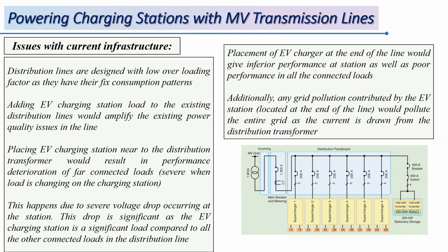As we know, distribution lines are designed with a low overloading factor since they have fixed consumption patterns. Adding an EV charger would further overload the existing system. And if you place a charging station near the distribution transformer, that would adversely affect the loads connected towards the end of the line.